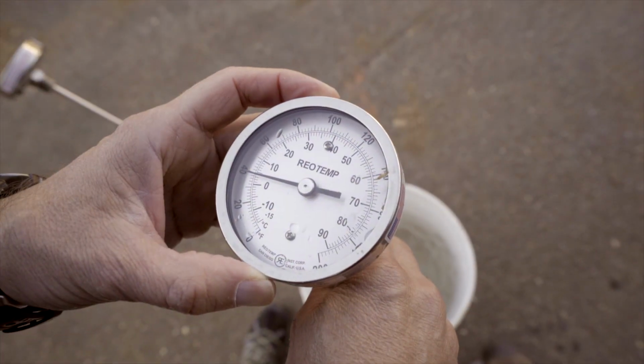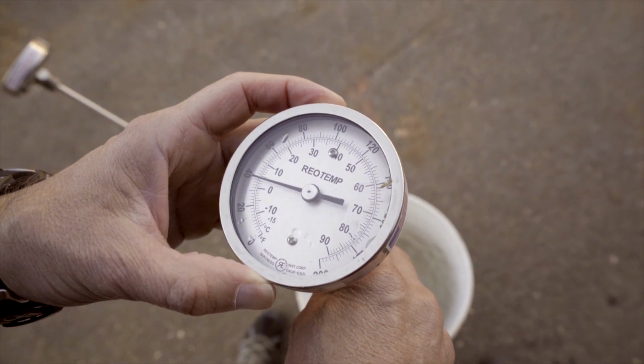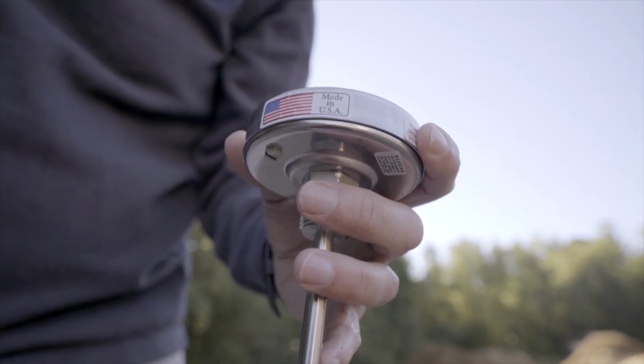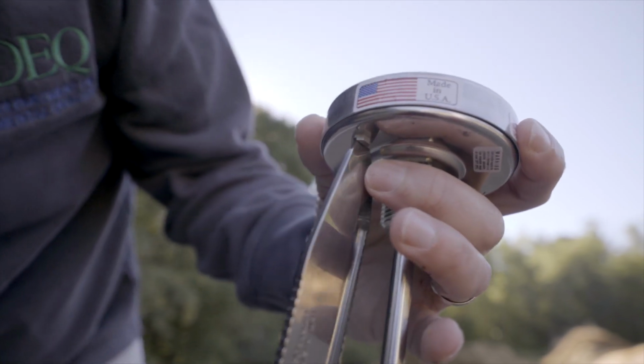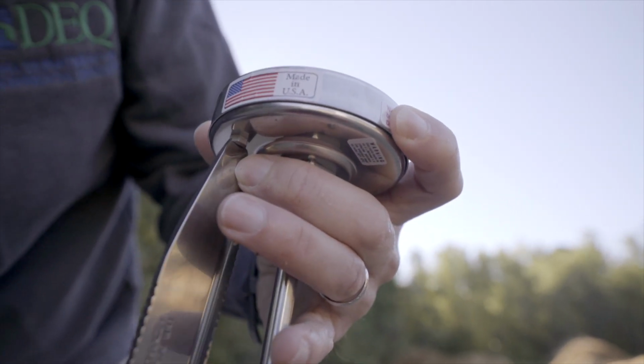And after that point, you can look at the readings on your temperature probes. If you're reading higher than 32 degrees, you can turn it down. If it's reading lower than 32 degrees, you can adjust it. There's going to be a dial on the back of the temperature probe that you can use to make those adjustments. Again, it's critical to make sure that you're reaching the temperatures that you need to inactivate the virus, and it just takes a few moments to do the calibration.